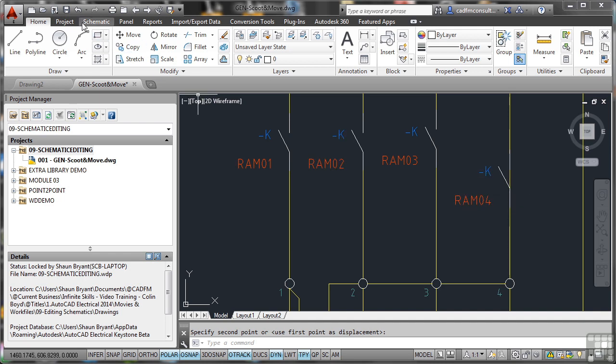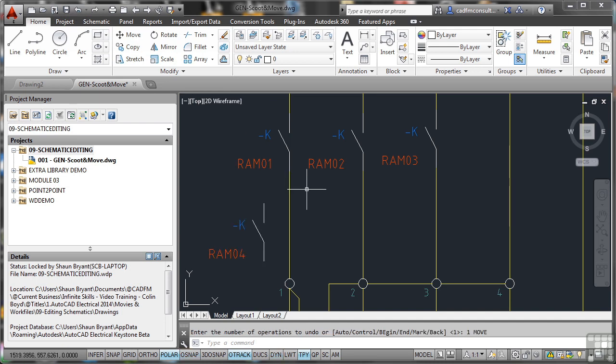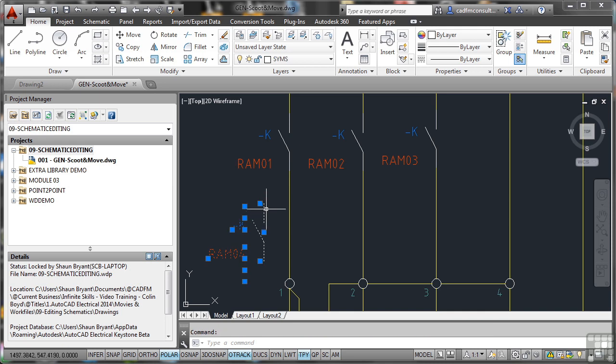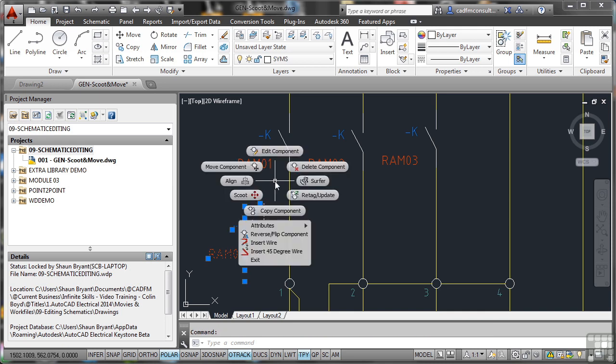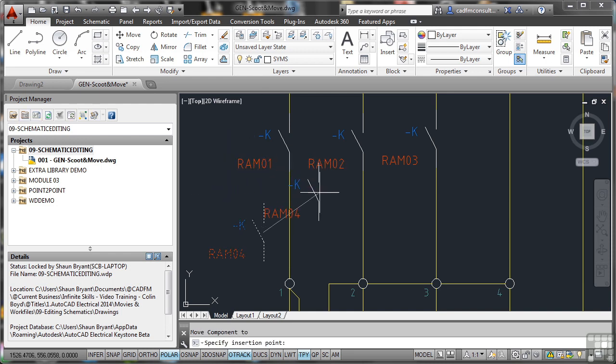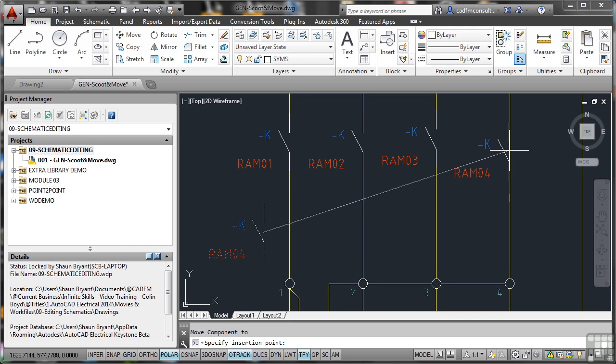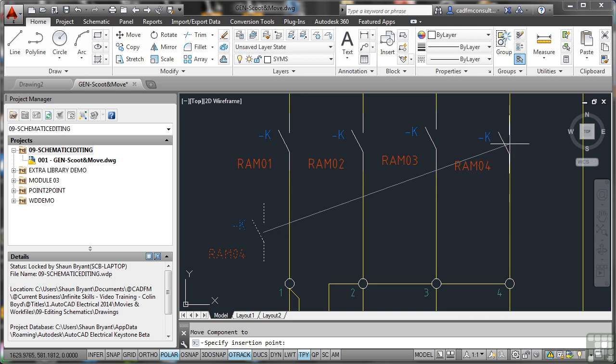Let's undo that. If I'm going to move a component in a schematic using AutoCAD Electrical, what I would do is use the move component command. That way, the drawing updates, the project updates, the database updates. So if I select that component and right-click, I get that lovely flashlight thing where you've got all the options available to you. There's move component. Move component is also available on the schematic tab on the ribbon. And now when I move it this time, I can drag.